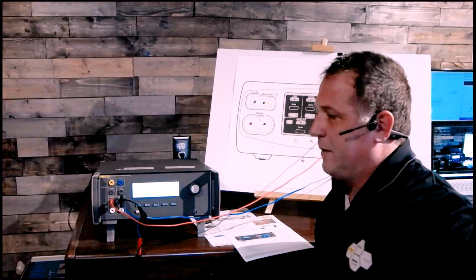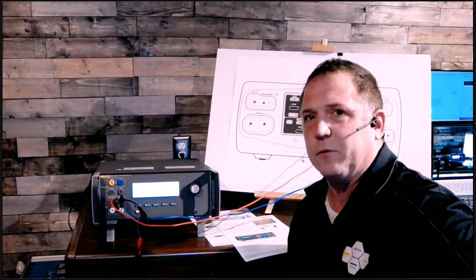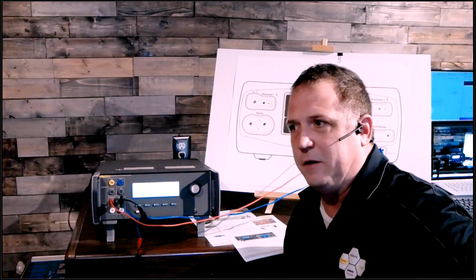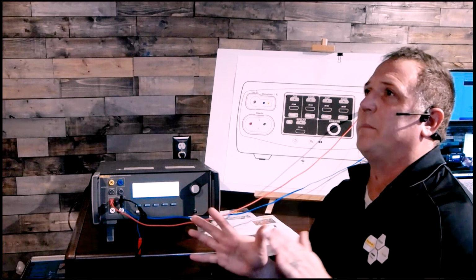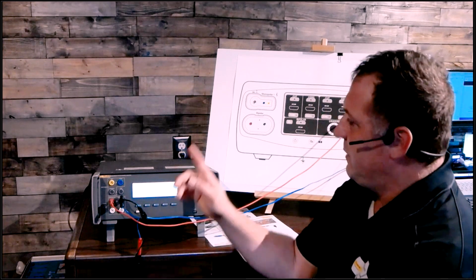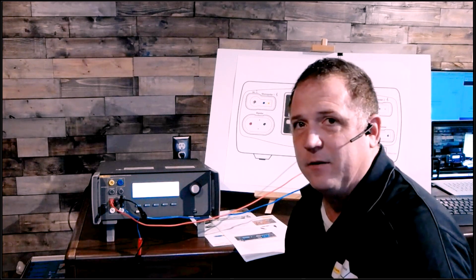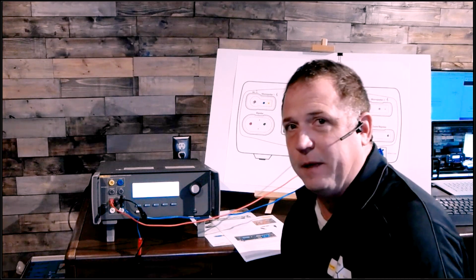How do you know if you made a mistake like that? Because all of a sudden you get wackadoodle readings that aren't within the spec of your service manual. Again, this is a great place to have your service manual open to know the exact resistance you're supposed to set and what your output reading should be.